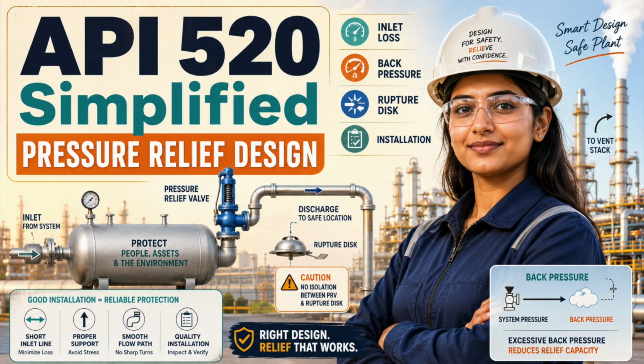Maximum allowable working pressure represents the actual permissible pressure capability of the completed equipment at the relevant temperature. Set pressure is where the relief device is adjusted to open. Overpressure is the increase above set pressure used to achieve relieving capacity. Accumulation is the increase above the equipment's maximum allowable working pressure during the event. Relieving pressure is generally set pressure plus permitted overpressure.